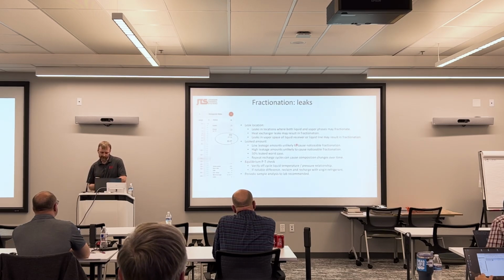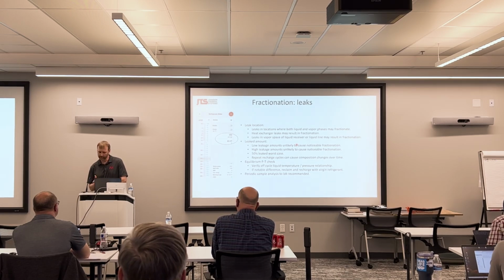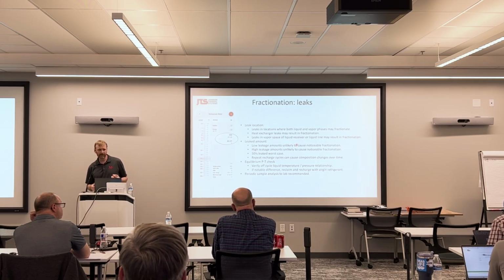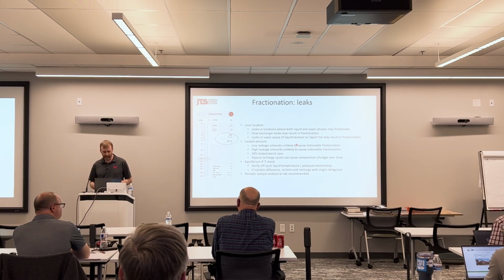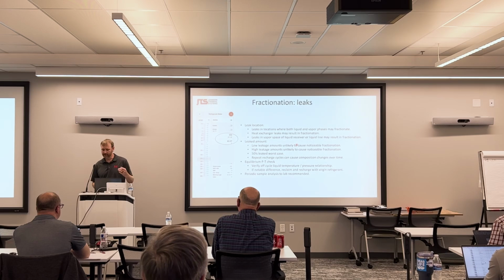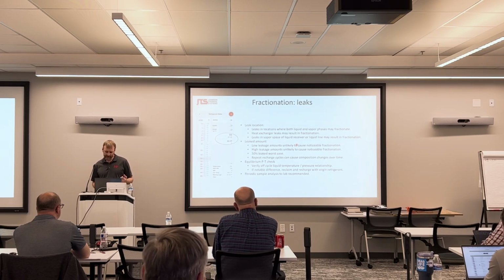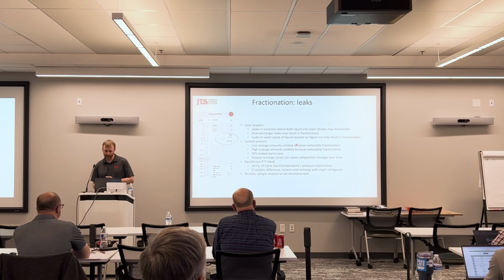All right, so leaks can also cause fractionation. If you happen to have a leak on a refrigeration system, the location of the leak could determine how much fractionation occurs. If the leak is on a vapor line, it's unlikely to leak one specific component. It's likely to leak both. If your leak happens to be in a location where both liquid and vapor phases exist, it's highly likely that you're going to leak the higher pressure component. So leaks on heat exchangers, leaks on your liquid line, and leaks in the vapor space near liquid receivers are highly susceptible to fractionation.